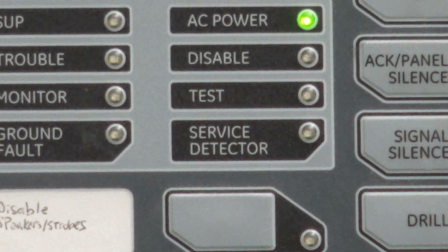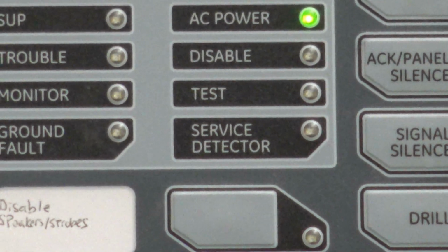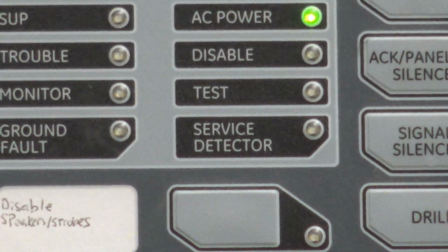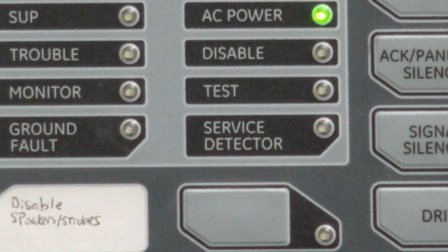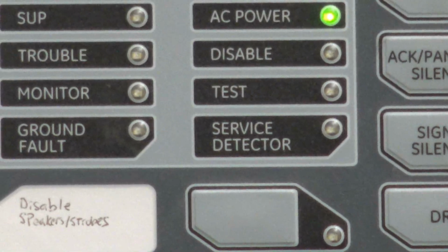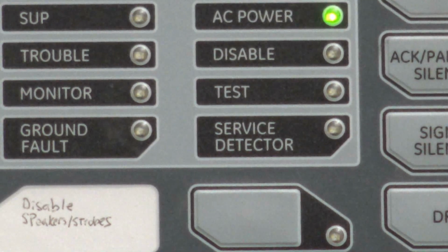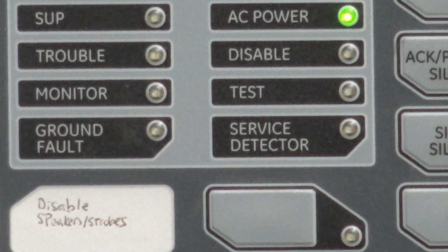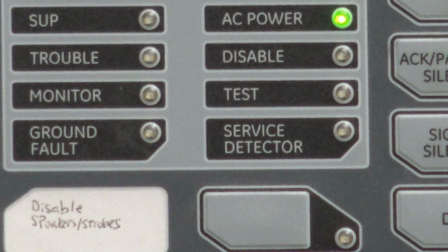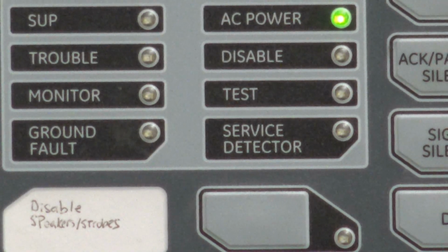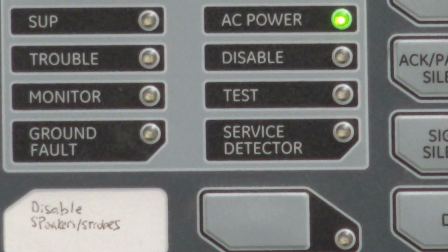It's just telling you it's dirty. I've seen some in maintenance alert above even 99%. I have one now downtown at Lebec Tower that's 99% dirty, and it still has not gone into alarm. These smoke detectors are intelligent, and they take samples of the air for 3 days, and they adjust to their environment.